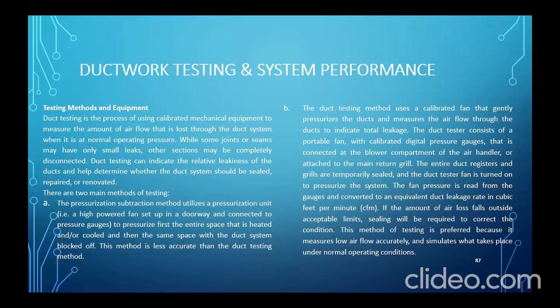A. The pressurization subtraction method utilizes a pressurization unit that is a high-powered fan set up in a doorway and connected to pressure gauges, to pressurize first the entire space that is heated and or cooled, and then the same space with the duct system blocked off. So this method is less accurate than the duct testing method. Ito yung pressurization mo sa room. Ayan.